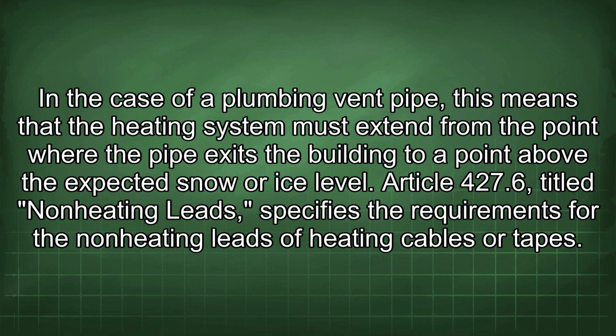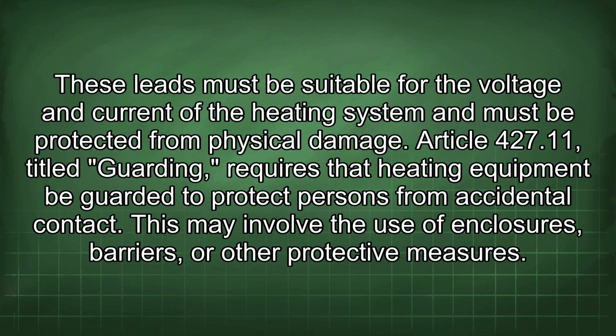Article 427.6, titled Non-Heating Leads, specifies the requirements for the non-heating leads of heating cables or tapes. These leads must be suitable for the voltage and current of the heating system and must be protected from physical damage. Article 427.11, titled Guarding, requires that heating equipment be guarded to protect persons from accidental contact. This may involve the use of enclosures, barriers, or other protective measures.